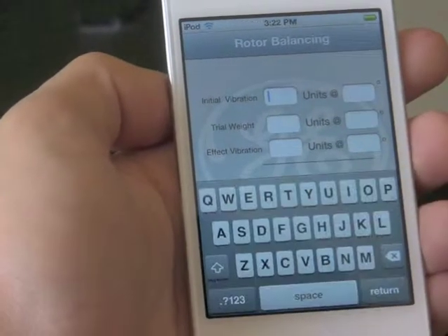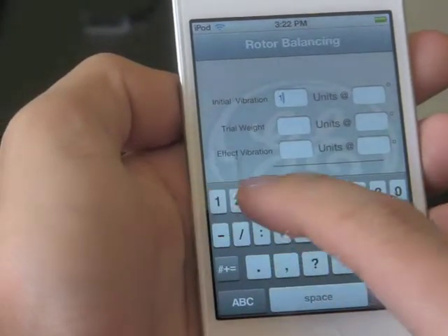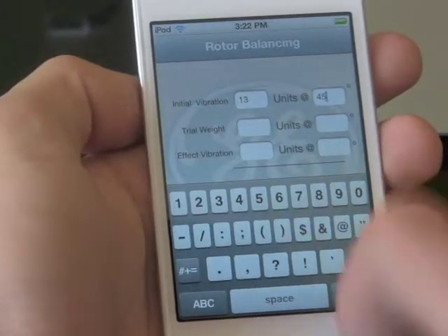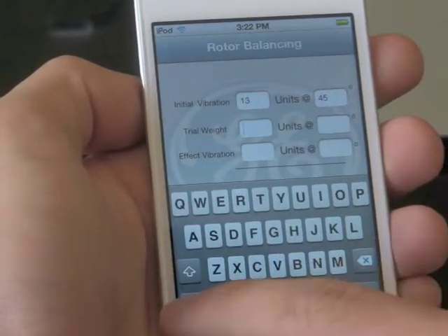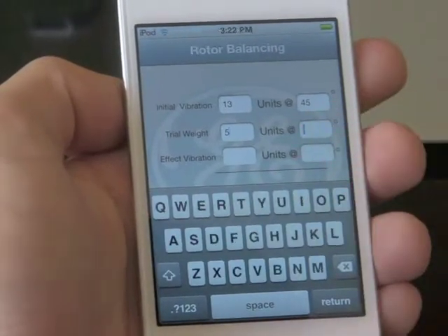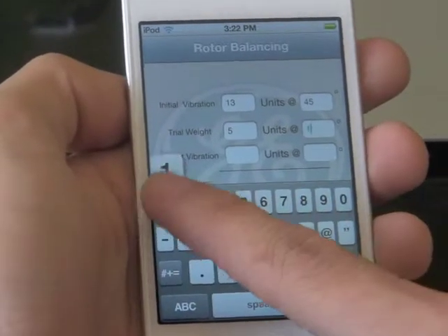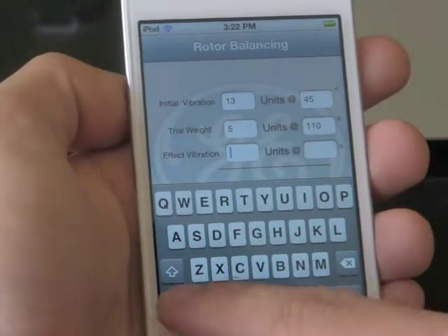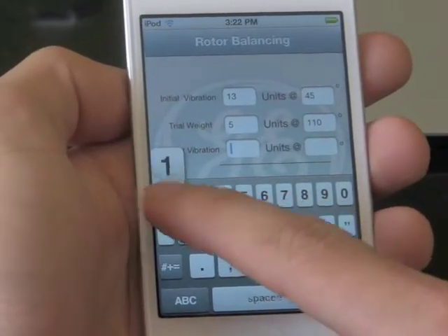GECCOS also provides the ability to perform rotor balancing, which is necessary for any generator to properly work without any safety risks. The user enters in key data received from System 1, GE's rack monitoring system, and GECCOS informs the user of what type of weight to place on the generator shaft, as well as the proper angle.